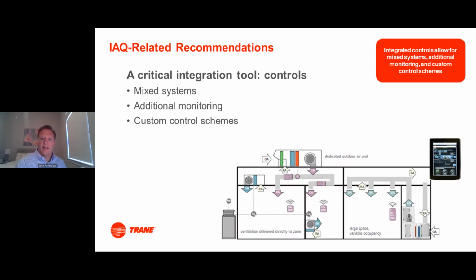The first piece I'd really like to highlight for the group is when we're talking about IAQ and VRF, a critical tool to achieve those outcomes of a healthier space and improved indoor air quality is your control system. We've got to have the data, and we've got to be able to pull multiple different levers to deliver on an outcome to really deliver on that healthier space. So, looking at mixed systems where you have a DOAS unit separate from your VRF system, obviously you have outdoor condensers separate from your indoor evaporators, and these can be heat pumps, they can be heat recovery. We've got additional monitoring we can do through controls, potentially custom control schemes. A lot of things we can do. If we don't have the control system that's actually tying all that together, then it makes it very difficult or not possible to do.